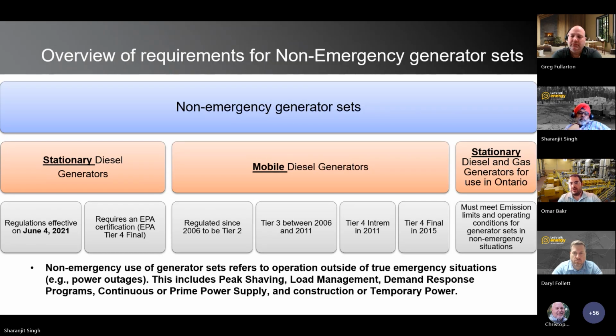This is on the federal level. For mobile generator sets, this regulation started back around 2006. As we progress from 2006 to 2015, the tier level of emissions that the mobile generator set must follow changes. It goes from 2006 standards to tier 3, then tier 4, then tier 4 final. So it must be taken on a case-by-case basis: when we look at a mobile generator set that will be used for a non-emergency situation, we must look at the year it was manufactured and see which emission levels it complies with.